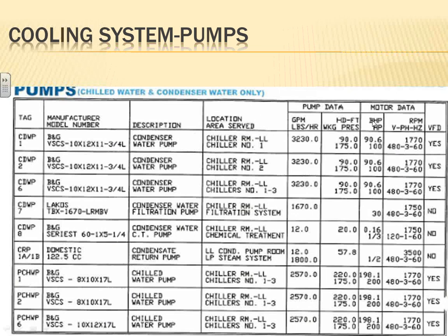Anybody know what the BHP is? I was struggling with that one. Brake horsepower. Brake horsepower. But we size based on the HP, horsepower. Brake horsepower is the horsepower they actually need to pump the fluid, and they are supposed to pick the next largest motor that will provide them that brake horsepower. Okay. That makes a lot of sense. So this is the mechanical horsepower, and then we go to the next standard size. Okay, so that makes a lot of sense.